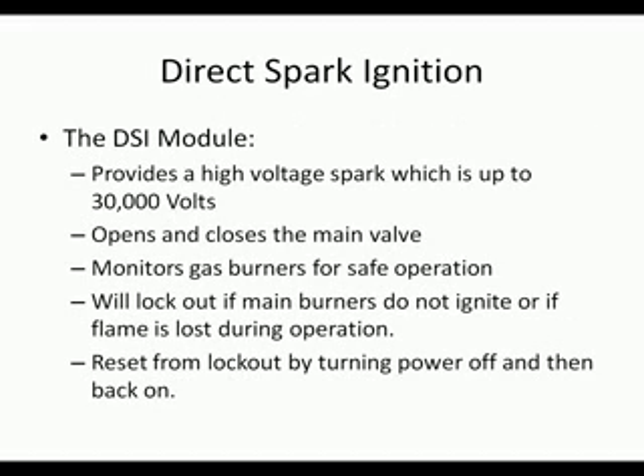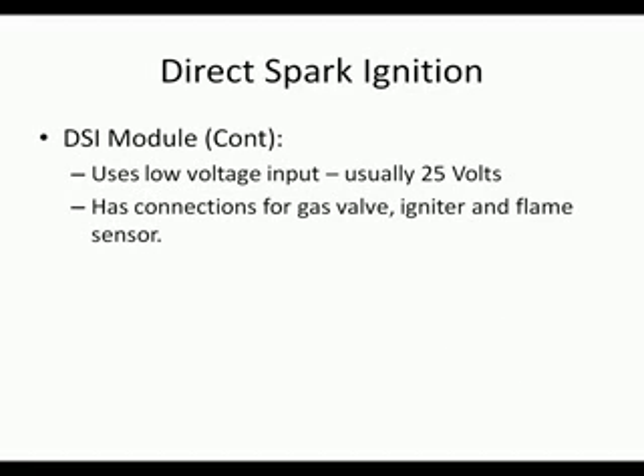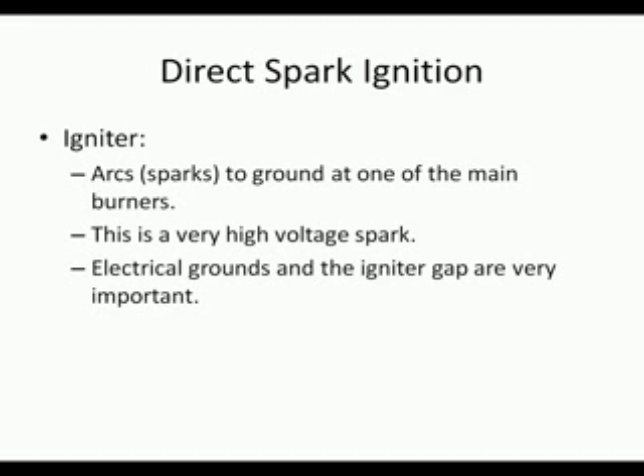The components that make up the system: again, you have to have your module, you have your igniter, you have a flame rod or sensor, and if it's part of the system, it's called a local sensing or single rod system. If it's a remote or separate rod, it's called a dual rod or remote sensing system. The ignition module provides a high voltage spark which is up to 30,000 volts. It opens and closes the main valve. It monitors gas burners for safe operation, and it will lock out if the main burners do not ignite or if flame is lost during operation. You can reset this lockout by turning the power off and then back on.